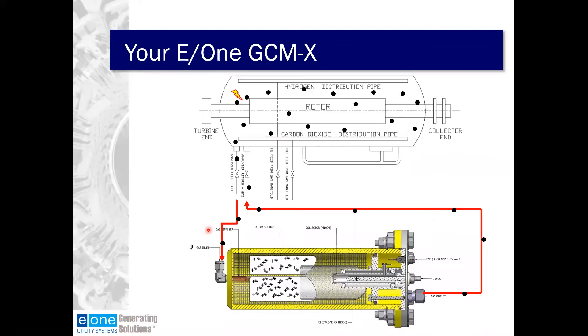When we have thermal degradation of organic materials inside the generator, millions of submicron particles are created. They go everywhere the hydrogen travels immediately. They'll begin to hit the ion chamber based on the flow rate and the distance from the generator. That's one of the reasons E/One recommends installing your GCMX as close to the generator as possible, often right on the turbine deck. Since these particles go everywhere in the generator, the GCMX will tell you if you've got an overheat problem, but it will not tell you where the problem is on its own.